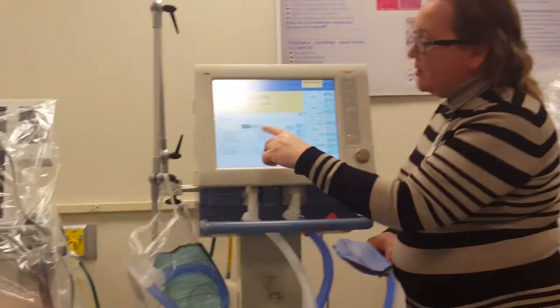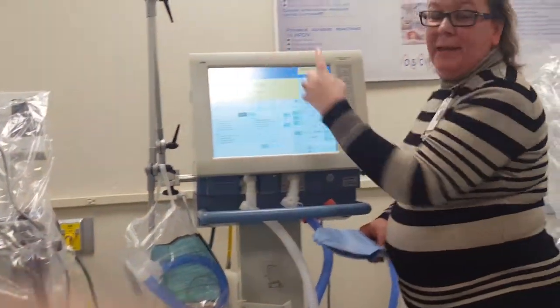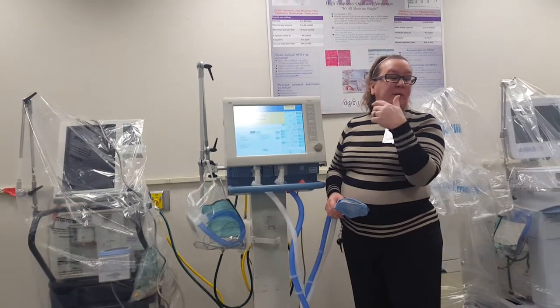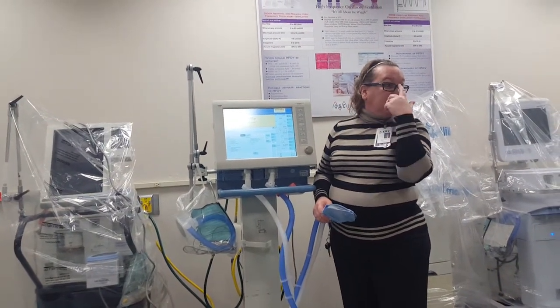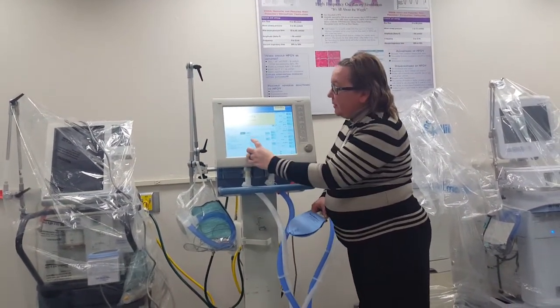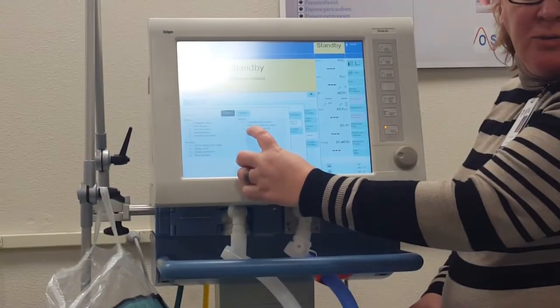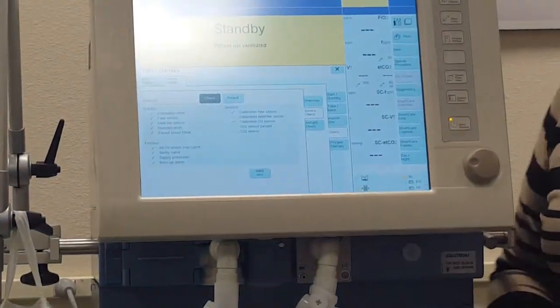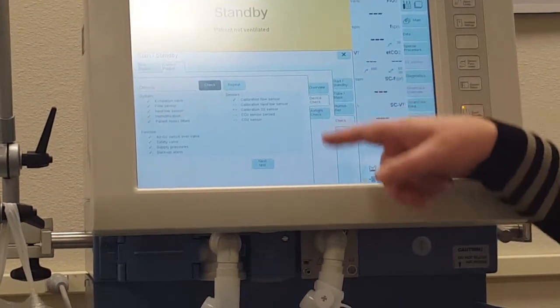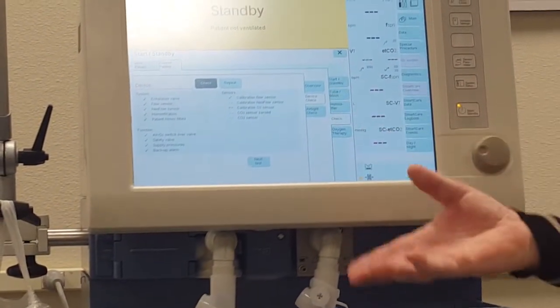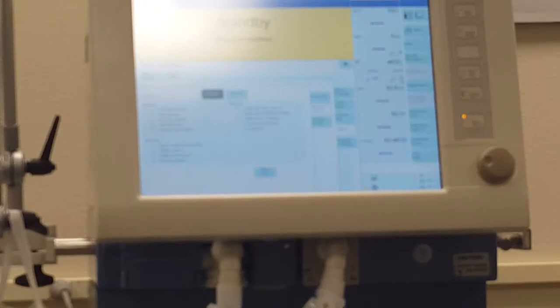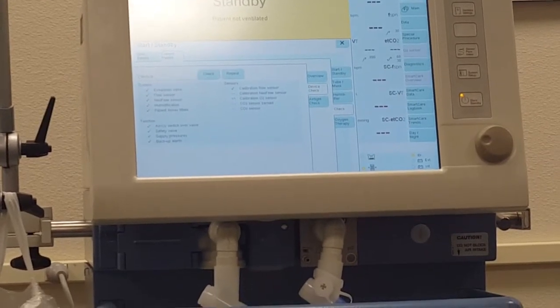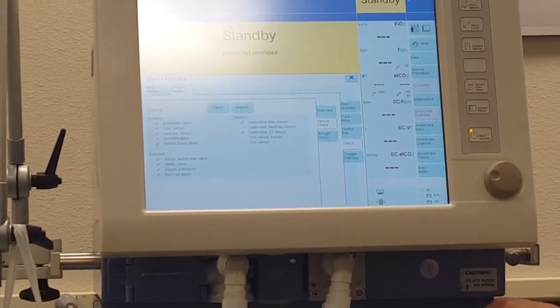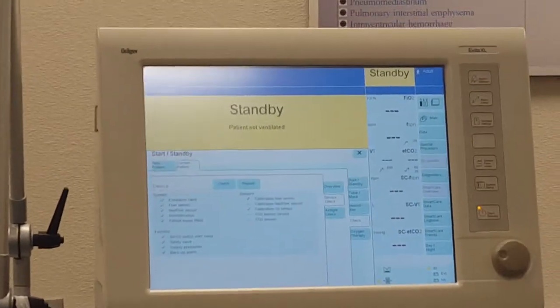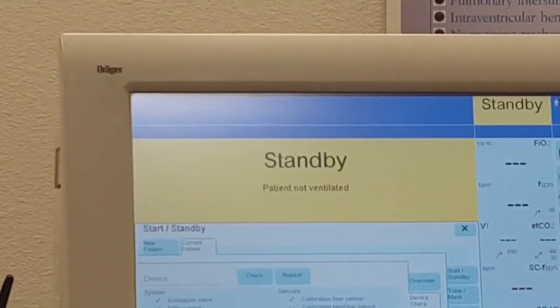Once this is done, you'll have check marks across all the screen, and you may or may not see the word O2 calibration OK come up. Sometimes you miss it. As long as you see all your check marks, including the one next to calibrate O2 sensor, you're passed. There are 2 ones past that for CO2 sensors, which we don't have hooked up because it's not on a person. So those will just have dashes. It knows that it's not hooked up, so it's not going to try to calibrate it. Calibration OK. So now that part's done.